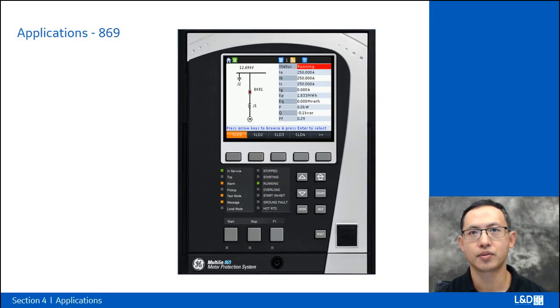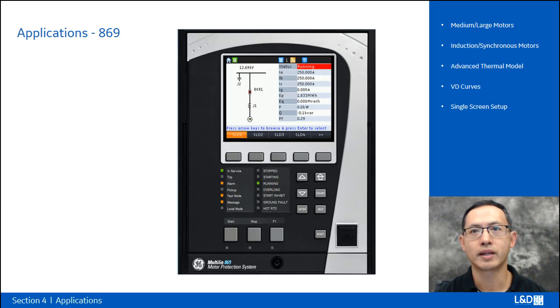869 has been designed for the protection, control, and management of medium and large induction and synchronous motors. Multilin 869 motor protection system offers a powerful solution for critical motor protection applications with an advanced thermal model and voltage-dependent curves for high inertia loads.